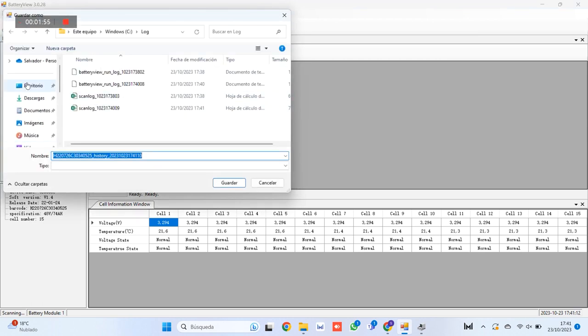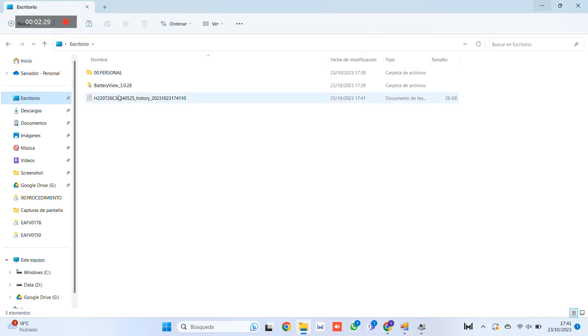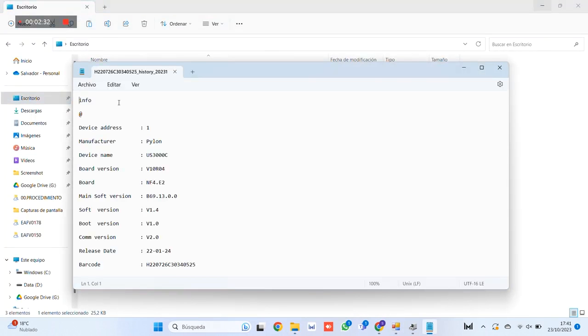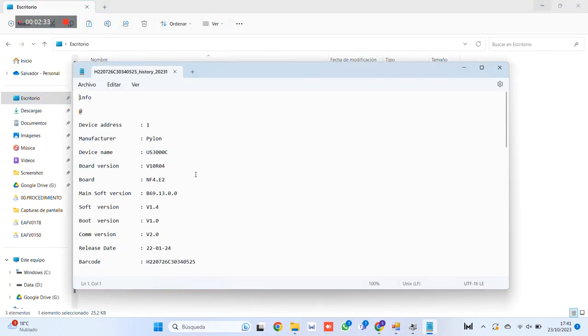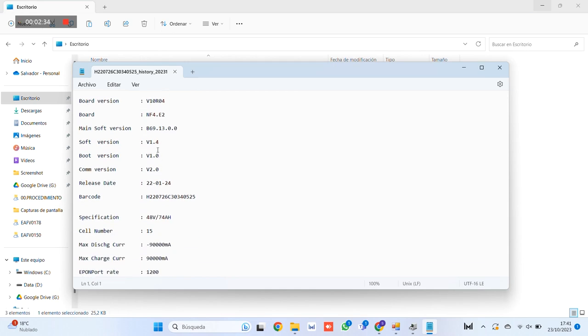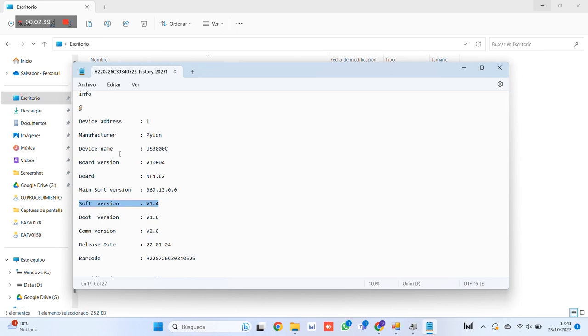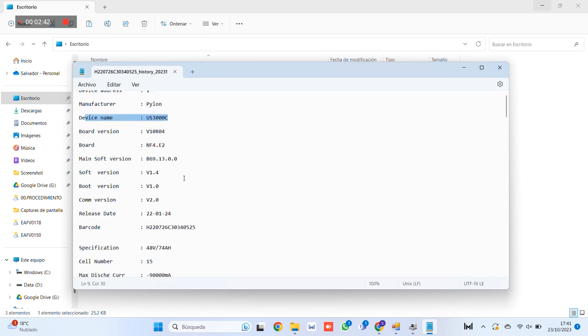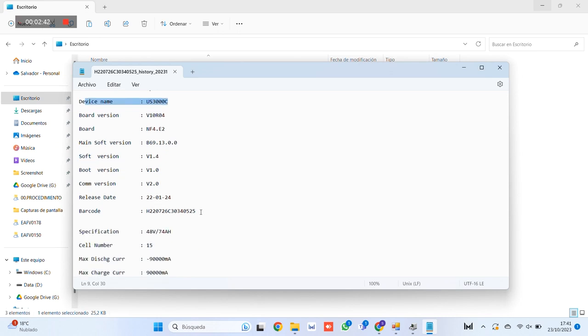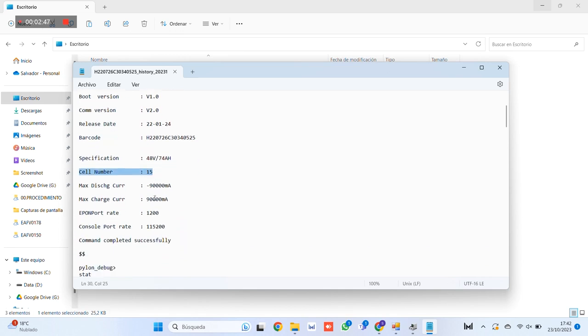The downloaded file is in text format, but if you open it, you can view some very relevant data, such as serial number, model, BMS version, software version, number of cells, etc. As a highlight, you can view the number of battery life cycles and the percentage of health of our equipment.